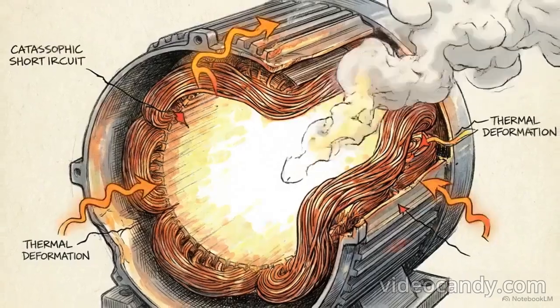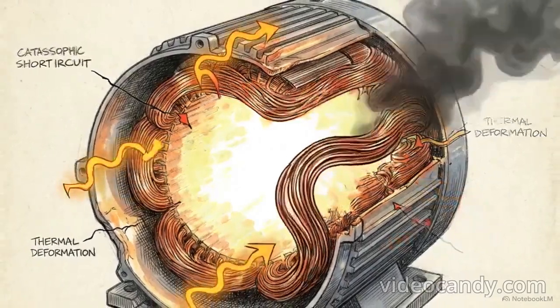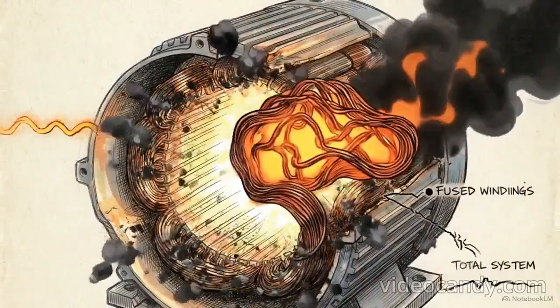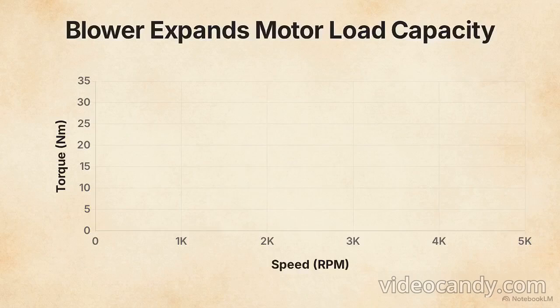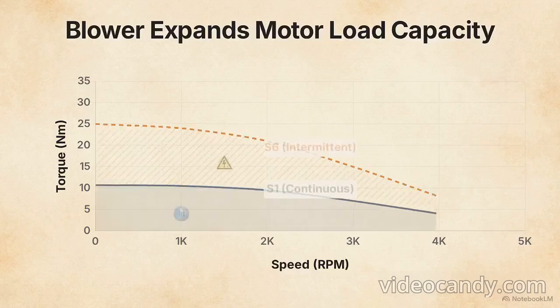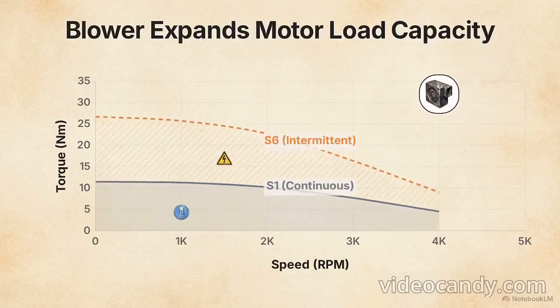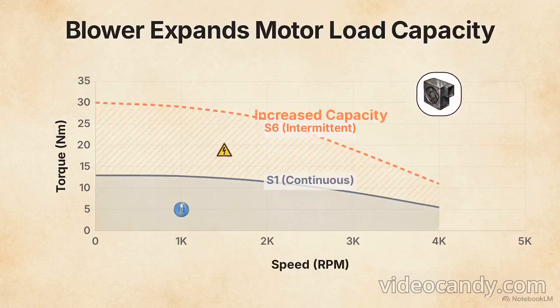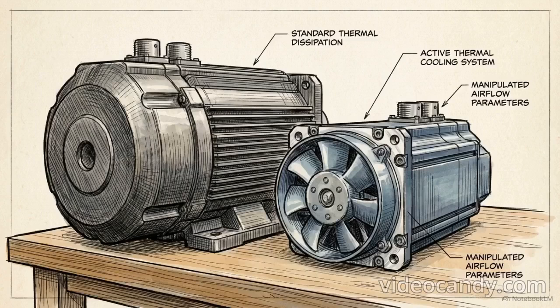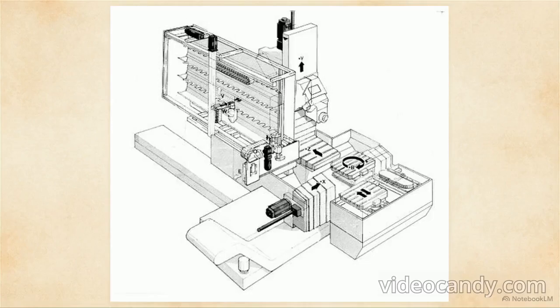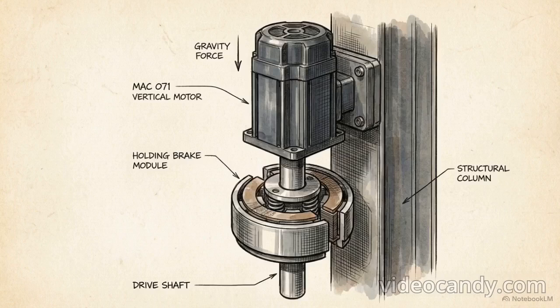However, running in the S6 zone is governed by a strict on-time percentage constraint. The motor can only sustain these high heat torque spikes for a specified portion of its total duty cycle, typically between 25 and 60%. Pushing into the intermittent zone too frequently without adequate rest forces thermal deformation of the internal components and leads to total system failure. Attaching a surface cooling blower alters this math. Forced air cooling physically shifts both the S1 and S6 boundary lines outward, increasing the maximum load capacity. By manipulating thermal cooling parameters, engineers expand a motor's operational boundary without having to install a heavier, larger frame size.